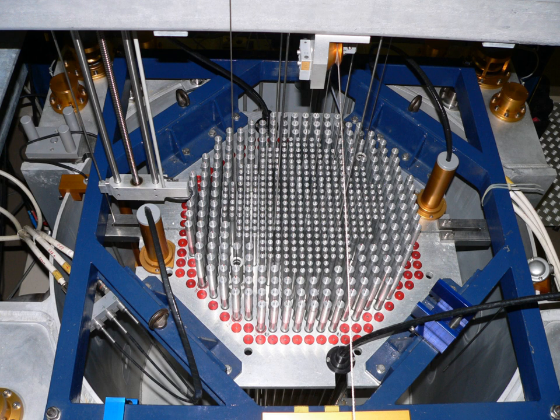The fastest method for adjusting levels of fission-inducing neutrons in a reactor is via movement of the control rods. Control rods are made of neutron poisons and therefore tend to absorb neutrons. When a control rod is inserted deeper into the reactor, it absorbs more neutrons than the material it displaces—often the moderator. This action results in fewer neutrons available to cause fission and reduces the reactor's power output.